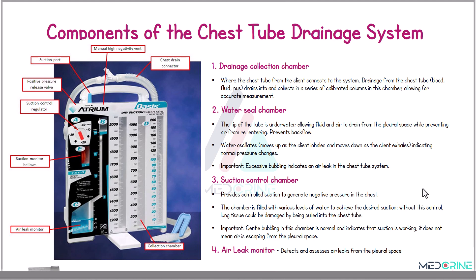The first component is a drainage collection chamber. This is where the chest tube from the client connects to the system. The drainage from the chest tube drains into and collects in a series of calibrated columns in this chamber to allow accurate measurement.